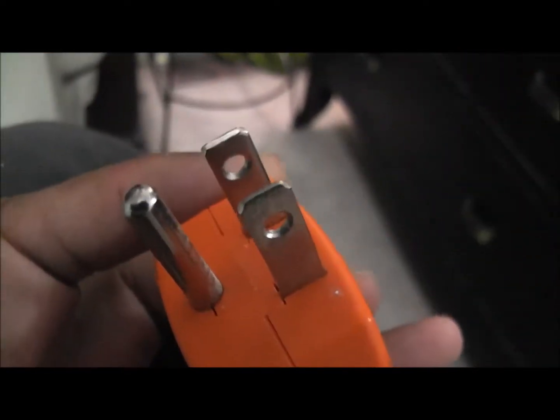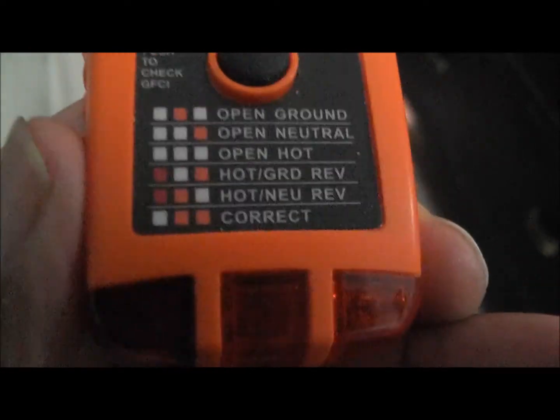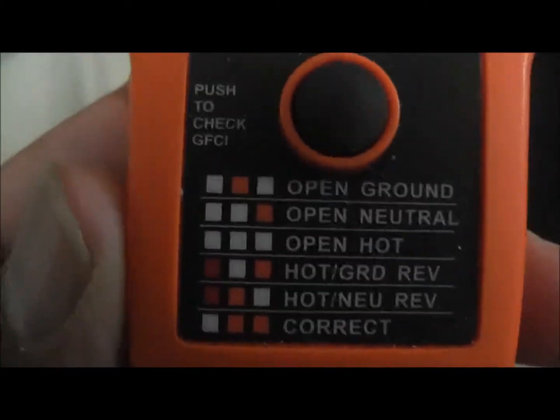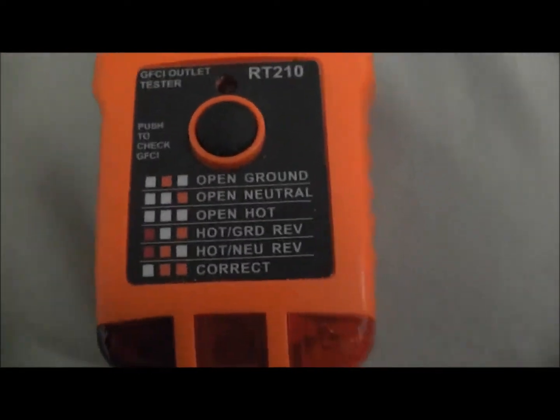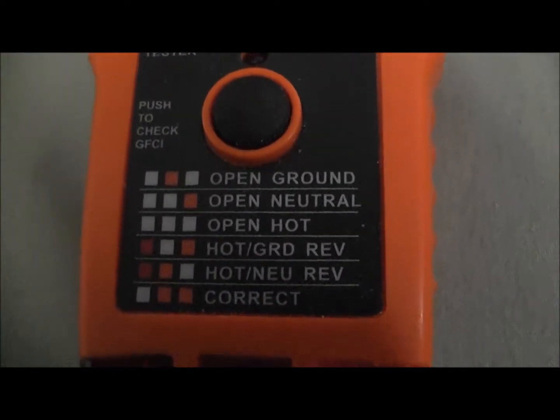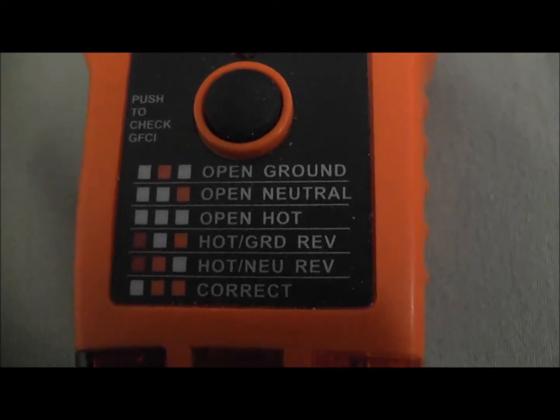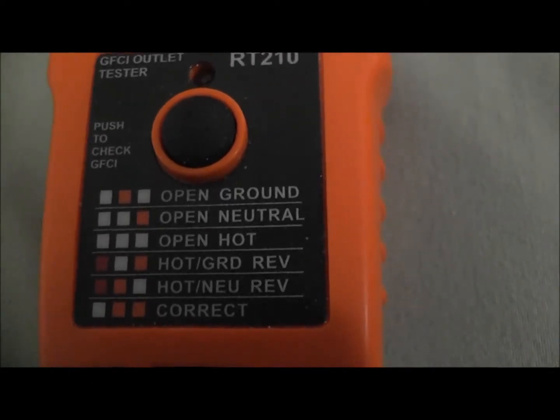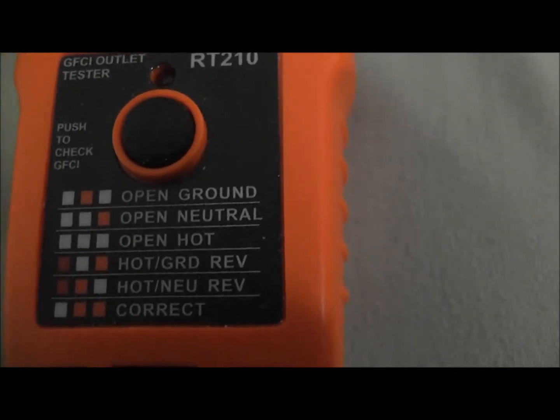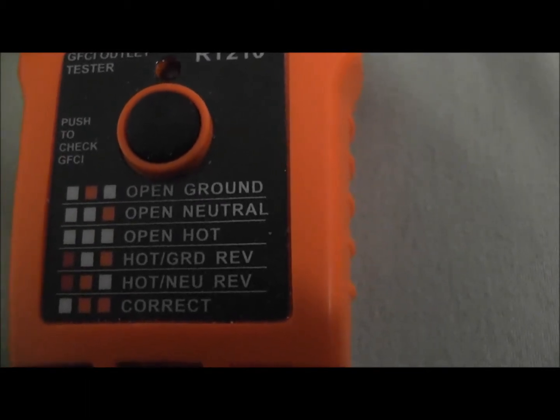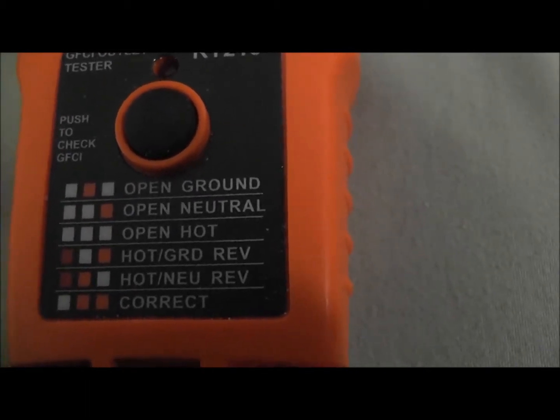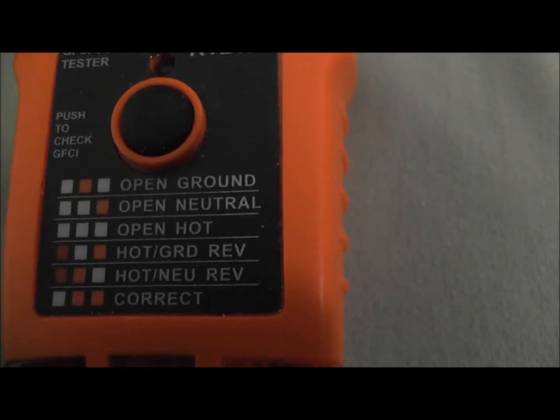So to test the multi-outlet tester, what you do is plug this into any mains outlet, and you've got three lights which come on, and it will tell you what's happened. The lights will come on depending what's happened. So the first example is open ground, that means there's no earth essentially. Open neutral means the neutral is not connected. Open hot means the circuit is basically dead.